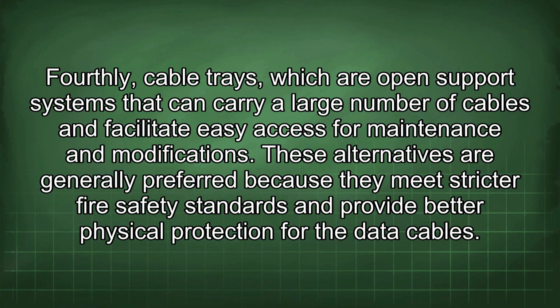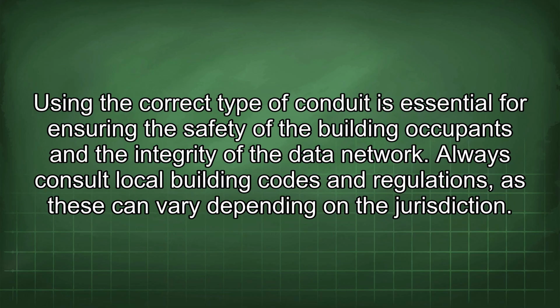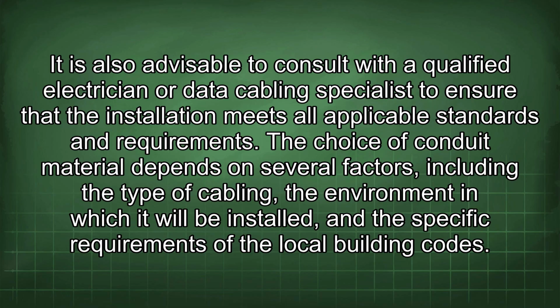Fourthly, cable trays, which are open support systems that can carry a large number of cables and facilitate easy access for maintenance and modifications. These alternatives are generally preferred because they meet stricter fire safety standards and provide better physical protection for the data cables. Using the correct type of conduit is essential for ensuring the safety of the building occupants and the integrity of the data network. Always consult local building codes and regulations, as these can vary depending on the jurisdiction. It is also advisable to consult with a qualified electrician or data cabling specialist to ensure that the installation meets all applicable standards and requirements.